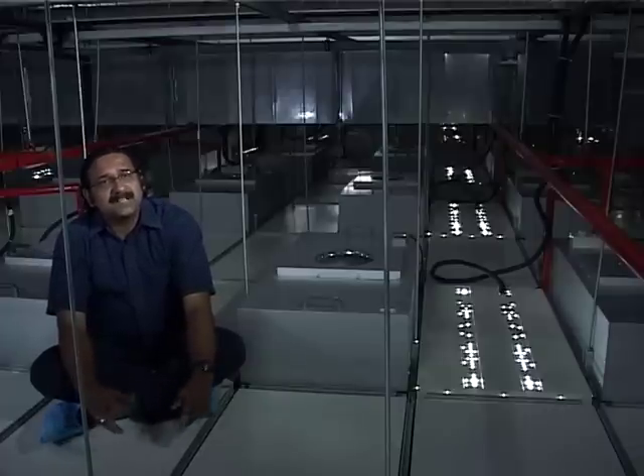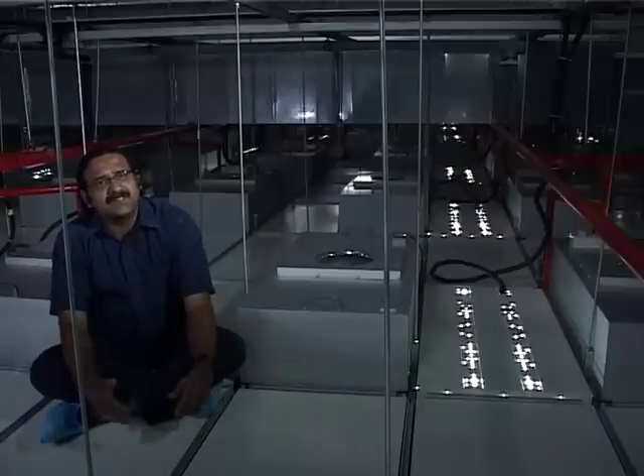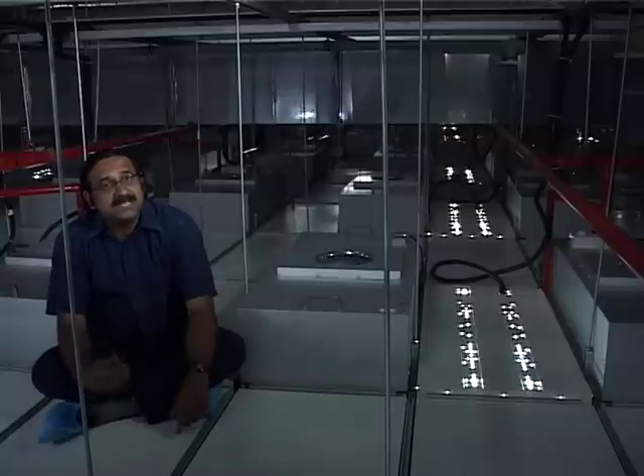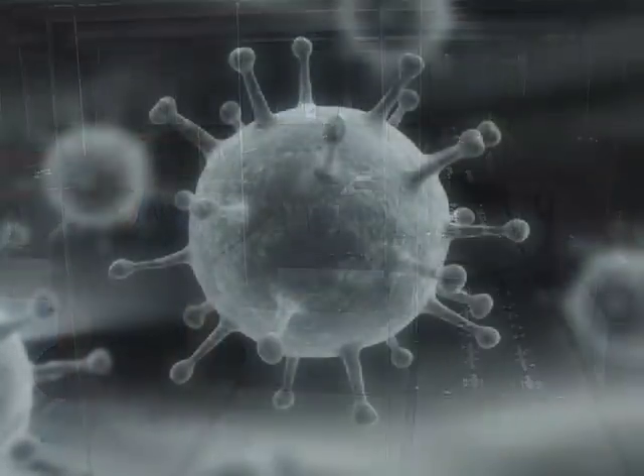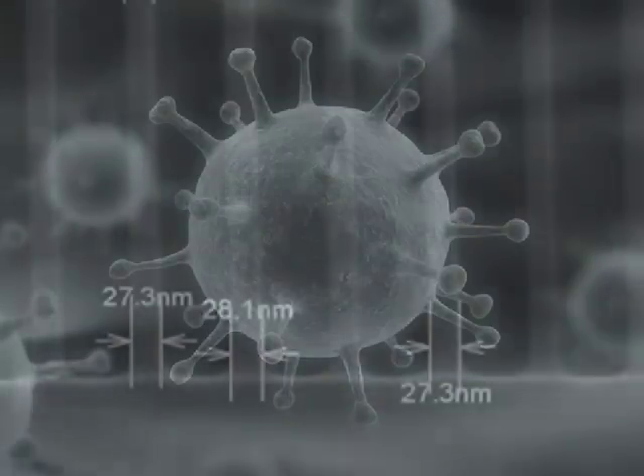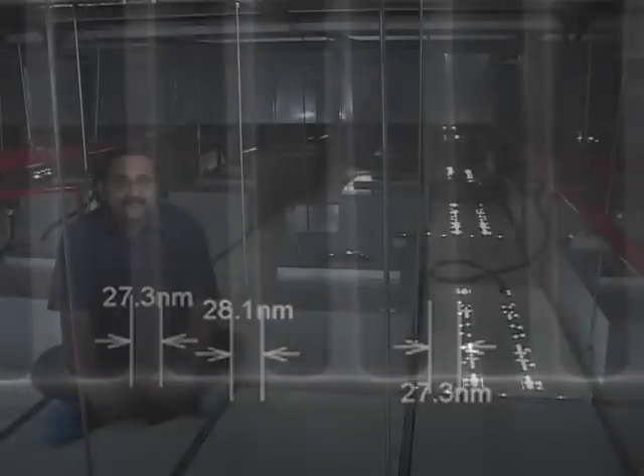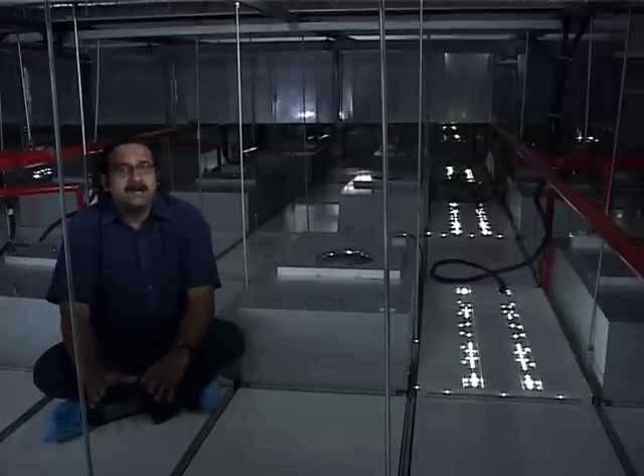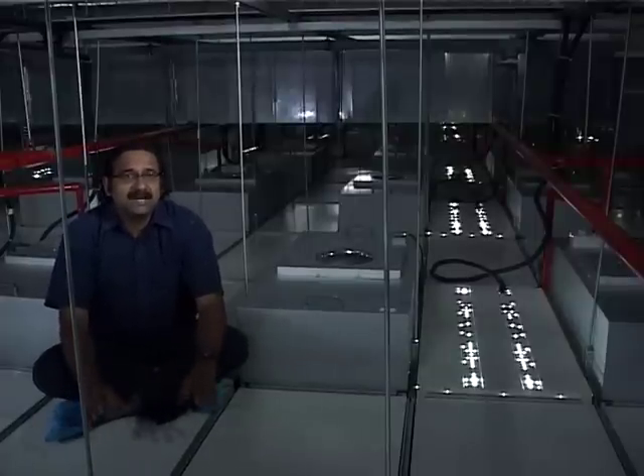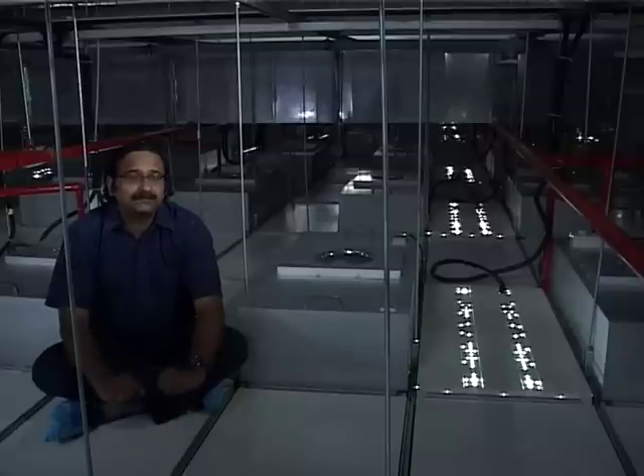The airborne particles are physical entities with a definite dimension. They have a particle size ranging from 1 nanometer to 100 micrometers. To get a perspective, think about an influenza virus whose size is 0.1 micron or 100 nanometers. In modern day technology, most of the transistors that are being used in a modern chip have a dimension smaller than this. Now this plenum area mainly controls the cleanliness within this clean room area.